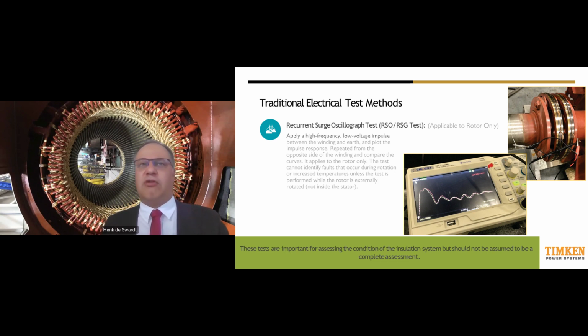A big advantage of it is that it can be done with a rotor installed, with a rotor outside. You can't do it while the machine is running, though. But one interesting thing that you can do is when the rotor is in a balancing bay and it rotates, if you use brushes that you supply onto the slip rings, you can actually perform this test while the rotor is rotating. Very, very important, especially after a rewind.